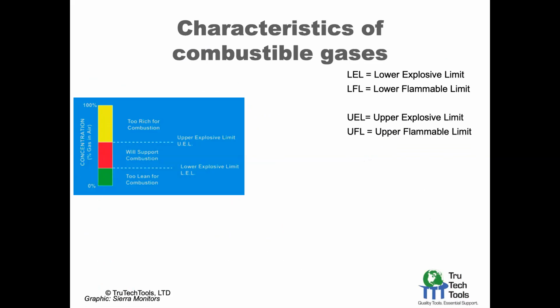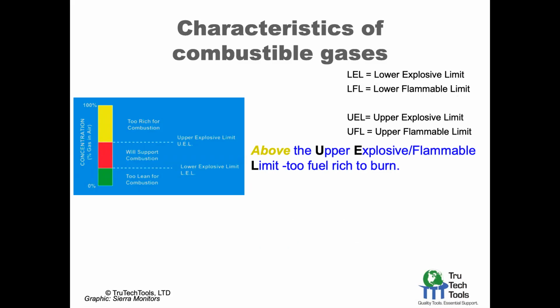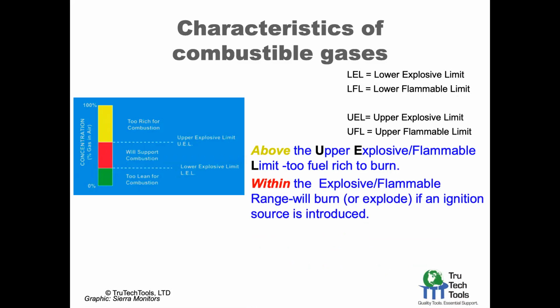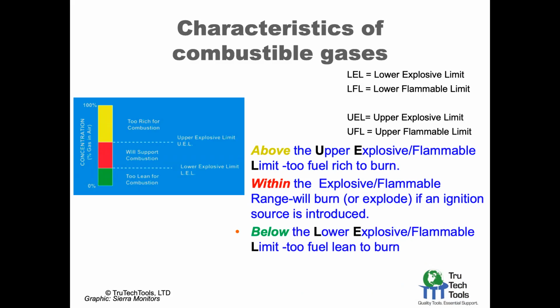Sometimes the lower explosive limit, the point where you go from too little fuel for the oxygen available to have any combustion into the explosive range, can also be called the lower flammability limit. So just for the trivia folks out there, LEL is the same thing as LFL. Then the upper explosive limit is the one you pass through in which you have too much fuel for the oxygen available. And at that point, you're not able to combust because the fuel to oxygen ratio is too high. Sometimes that's called the UFL, or the upper flammability limit. So above the upper flammability limit, or upper explosive limit, it's too fuel rich to burn. Within the middle range where it supports combustion, it can burn or explode if an ignition source of heat, spark, or flame is introduced. And below it, it's too fuel lean. There's not enough fuel for the oxygen available to burn.